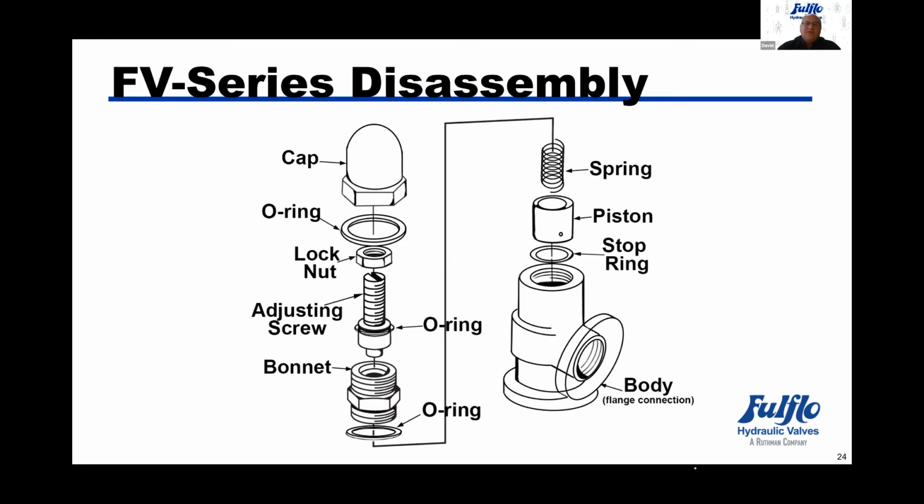Where the V notches, the old design, would allow the fluid to go through those V notches in the 4 different quadrants as the valve is opening and closing. So the new style of piston, flat bottom, is superior to the old design. With better technology, we're able to make that happen.